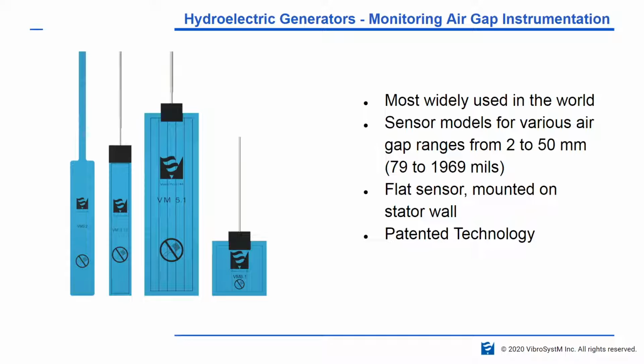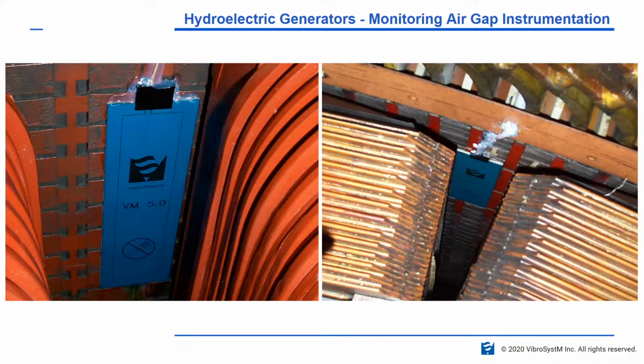In regards to air gap, as I mentioned, there are a few models. It all depends on the size of the air gap. The one on the left is very small, from 1 to 10 millimeters. The second one is from 2 to 20 or 2 to 25 millimeters. The third is from 5 to 50, and the one on the right, depending on the conditioner, is 5 to 50 or 5 to 35, if I remember correctly. They're flat sensors mounted on the stator wall, and it is patented technology. So we have some examples here of sensors which are installed.